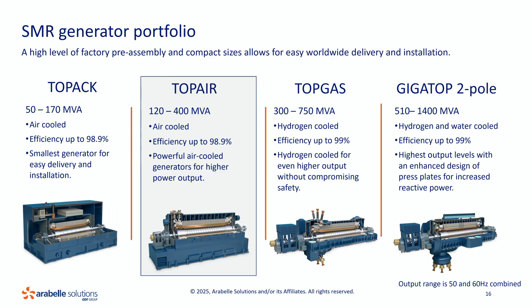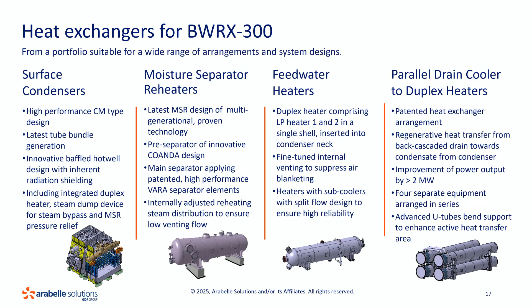I also take the opportunity to show you the heat exchangers which we have supplied to the Darlington project. First is the condenser. It's a very innovative design, and this kind of design is already put into a Leibstadt project in Switzerland, and compared to traditional design, it's 20% more efficient. Then we have the moisture separator. It also comes with a patented technology called VARA, which means variable amplitude across the chevron plates, and that gives better efficiency and lower pressure drop in the MSR. Then we have the feed water heaters, and in Darlington, we implemented another patented technology from Arabelle Solutions, a drain cooler in the parallel circuit, which gives around 2 megawatt more to the whole power plant.